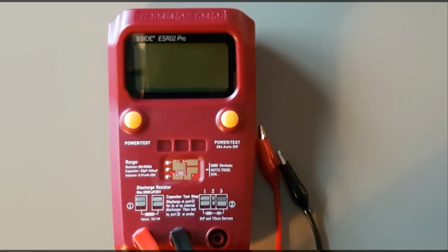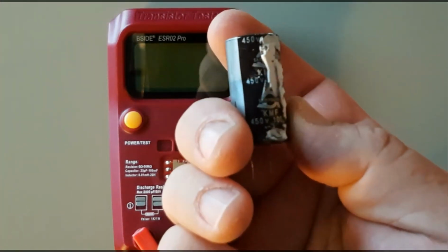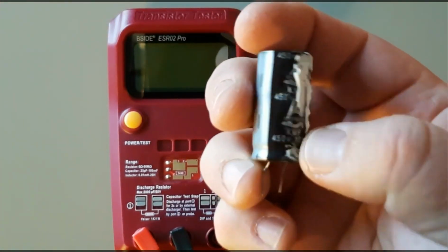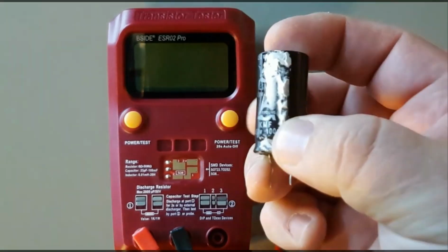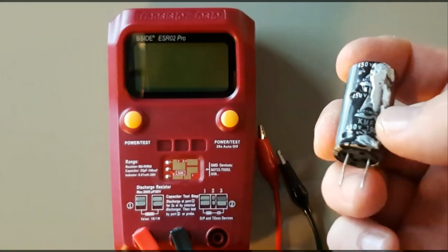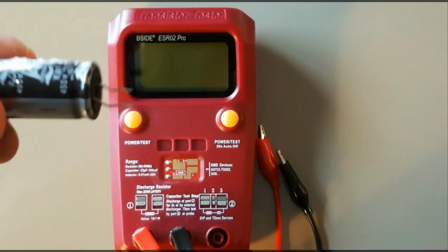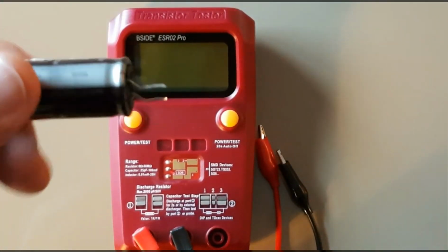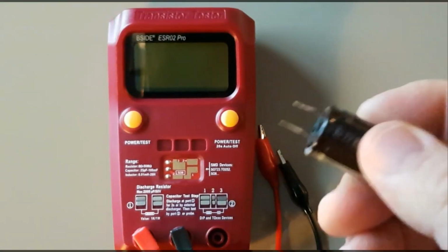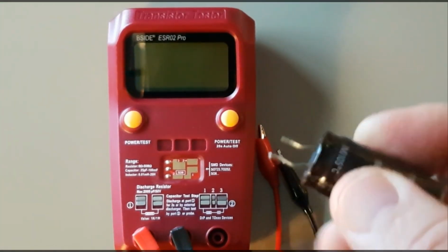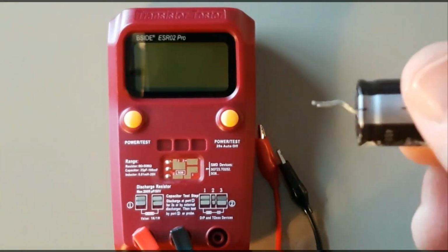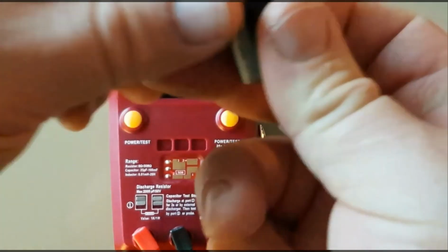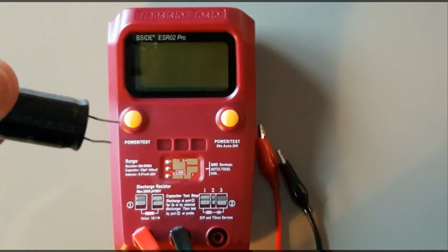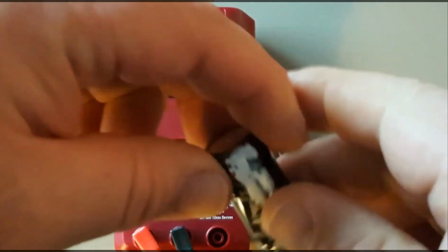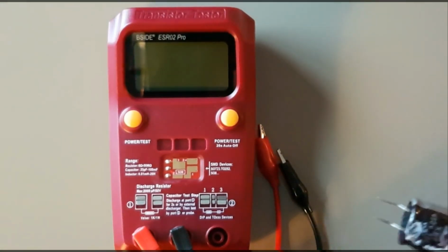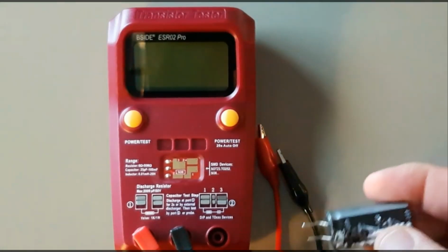Okay, so the next capacitor we're looking at today is a 100 microfarad once again, but this is a 450 volt capacitor. Now, a quick disclaimer, please discharge your capacitors. Make sure they are fully discharged before you do any sort of measuring or touch them, because anything over 50 volts can kill you. And at the same time, this type of voltage can also kill your meter. So discharge the cap.